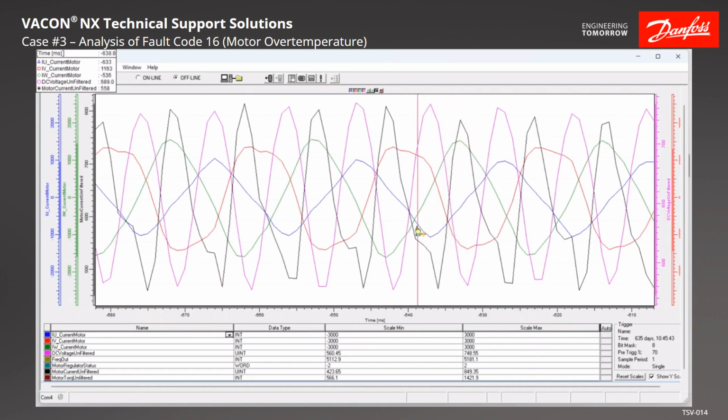We're also pushing more current on the output. It's waving up and down here, and you can see that when DC bus is up about where it should be, we're only putting out about 542 amps on the output. When DC bus is down at the bottom, where it shouldn't be, at that low DC bus, we're now putting out 781 amps. So we're pushing a lot more amperage through the drive than what we should be. So this would be pretty tough on the drive, and will definitely shorten the life of the drive. Your capacitors won't live long this way. You will overheat them and they will fail in a grandiose fashion.